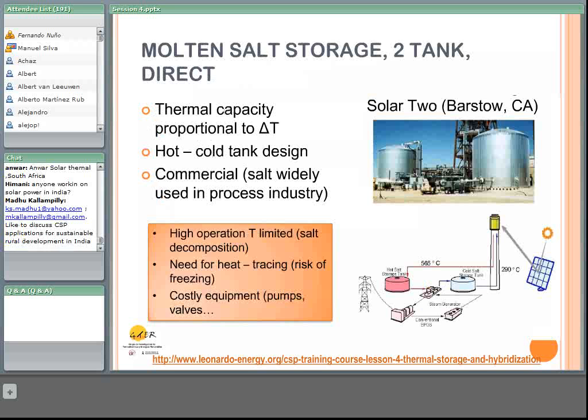It could be also liquid sodium, but sodium has some important safety problems, so normally it's not considered for these applications. But with molten salt, this problem doesn't exist. The thermal capacity of the tanks is proportional to the temperature difference between the hot and the cold tank. The design is a 2-tank design, and the molten salt mixture which is used in these systems is a commercial material, which is commonly used in the process industry.